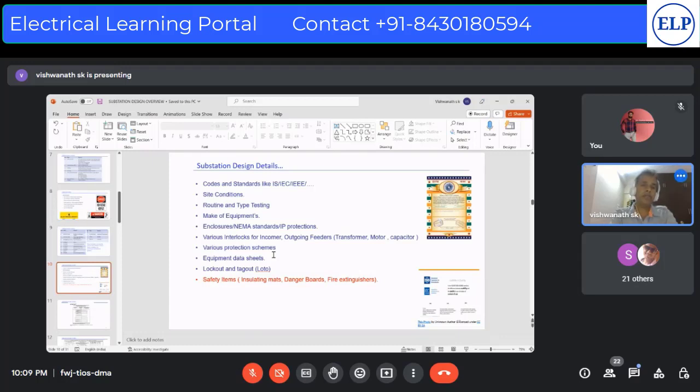Maybe you are hearing this for the first time, it's okay, but this is one of the important functions. Not everyone will go and test the design of a panel as per seismic. It basically talks about the vibration of the panel when seismic activity occurs, basically an earthquake, so that the components should remain intact with the panels.